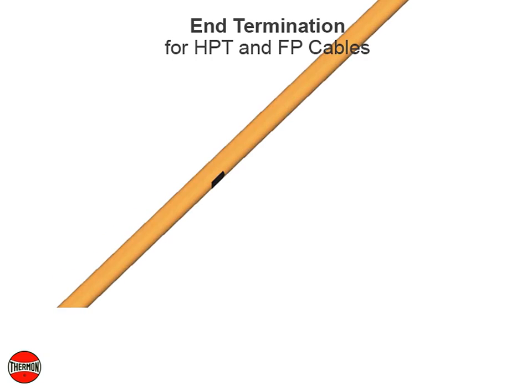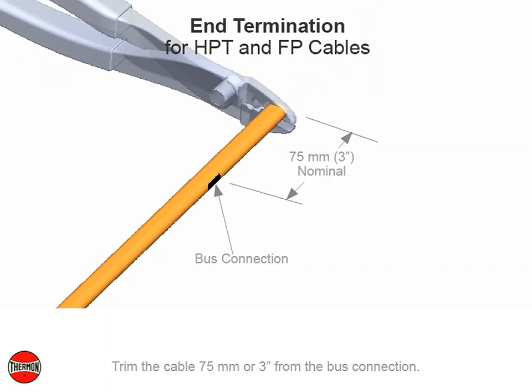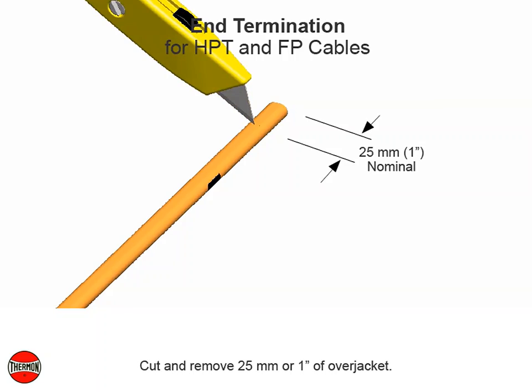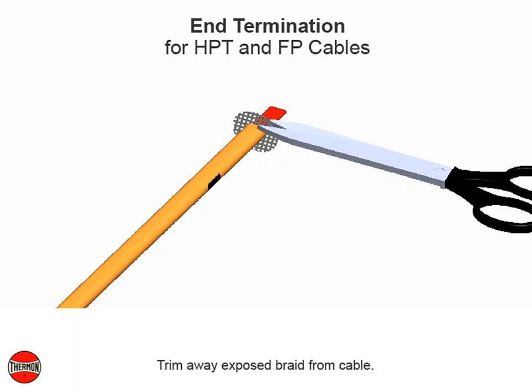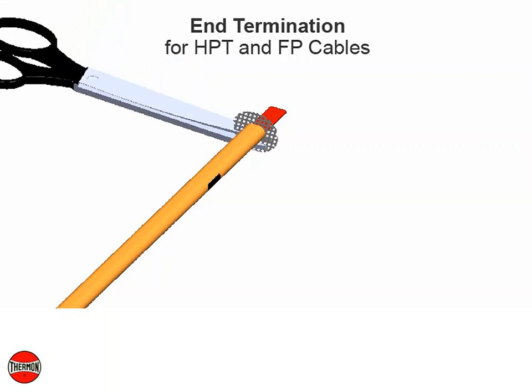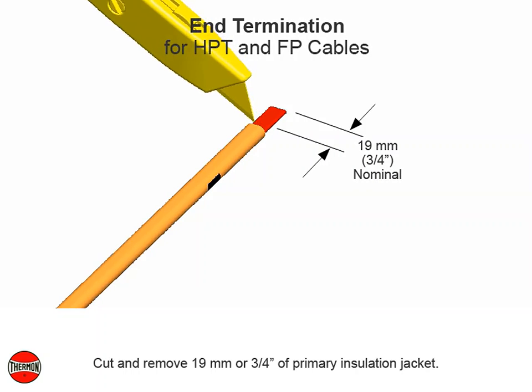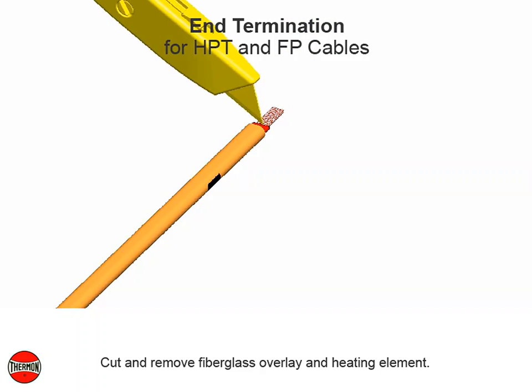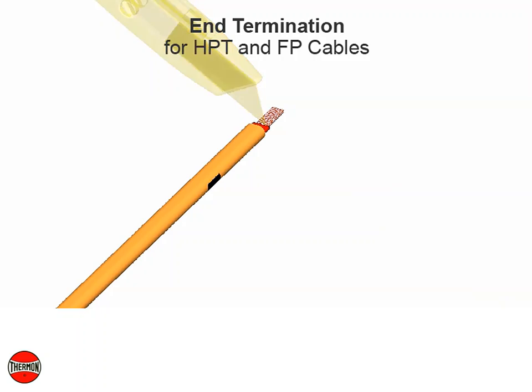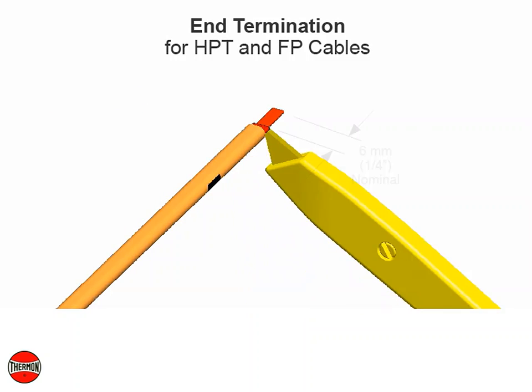End termination for HPT and FP cables. Trim the cable 75 millimeters or 3 inches from the bus connection. Cut and remove 25 millimeters or 1 inch of over jacket. Cut and remove fiberglass overlay and heating element. Trim away exposed braid from cable. Cut and remove 19 millimeters or 3 quarter inch of primary insulation jacket. Cut and remove fiberglass overlay and heating element. Push any remaining heating element wire under the primary insulation jacket. Cut and remove 6 millimeters or 1 quarter inch of pairing jacket.